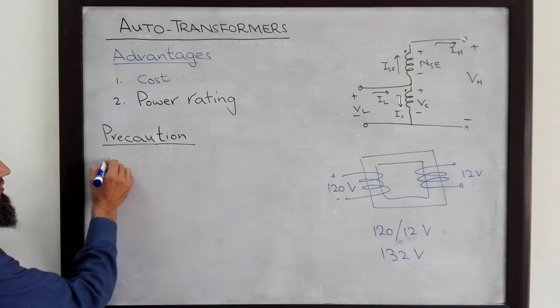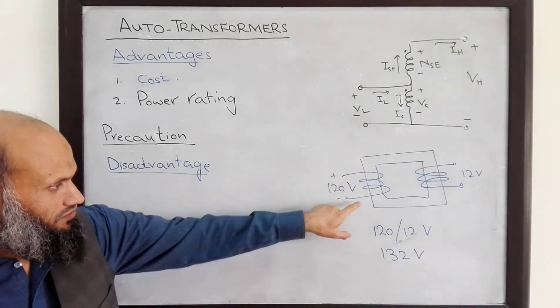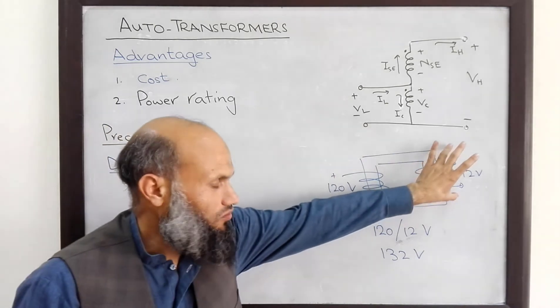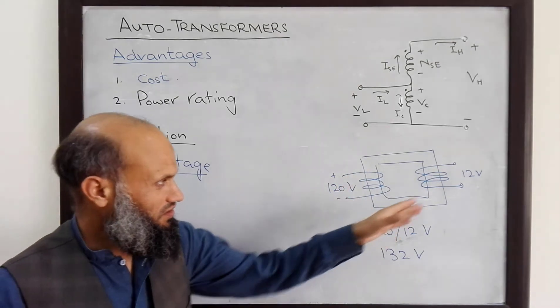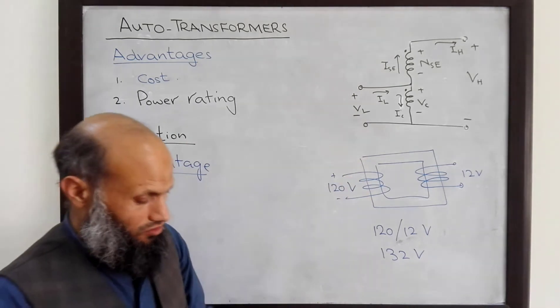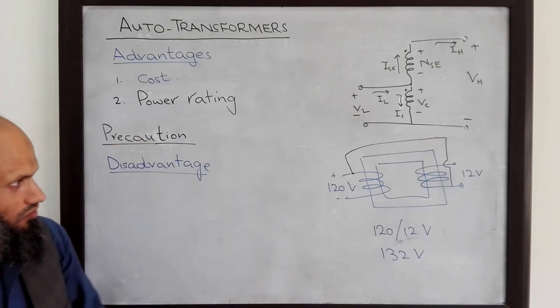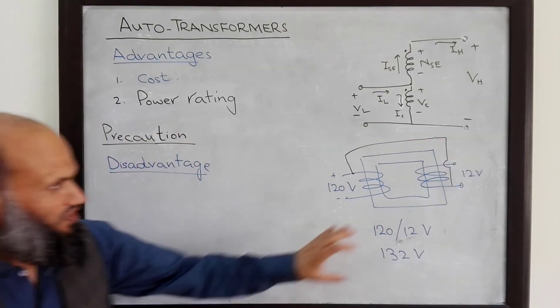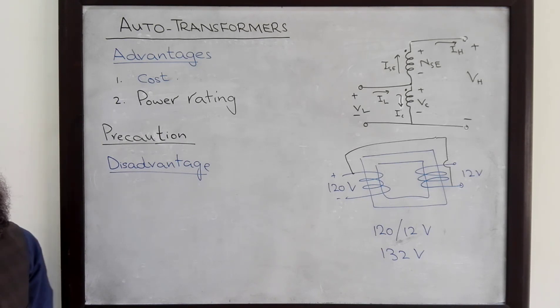There is a key disadvantage of an auto transformer. In a conventional transformer, there is no electrical connection between the primary and secondary windings, so high voltage and low voltage are electrically isolated from each other. If there is any noise on the primary side, it is not directly transmitted to the secondary side. However, in an auto transformer configuration, there is an electrical connection, so noise on the primary side will be transmitted to the secondary side. Therefore, with an auto transformer configuration, we lose electrical isolation.